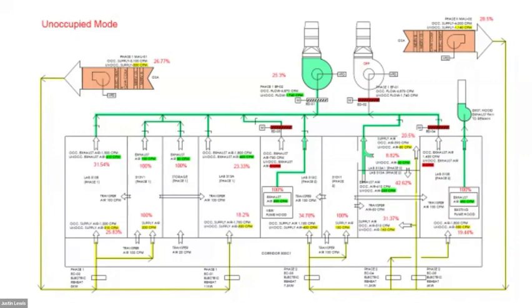But when we start looking at the numbers, we saw that this was really going to have a problem. So again, no VAVs, no air valves. If we look at MAU1, which serves three rooms, the unit ramps down to about 27% of the occupied flow in the unoccupied mode. However, we have a range from 18% all the way up to 100% airflow maintained in each room. Without VAVs, without air valves, that's just not going to happen. The same situation with MAU2, which has more distribution and quite a few different ranges. Exhaust fan, same deal.